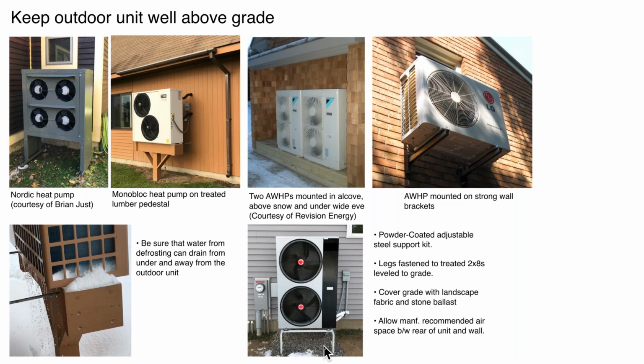And then just to show you what happens with one of these units when it goes into a defrost, if you look over here on the left, lower left, if you look carefully, you can see the water pouring out of the bottom of that unit. If that unit is just sitting on a concrete slab, what can and has happened is that water will tend to accumulate in the bottom of that unit. It won't fully drain away, or it'll run out of the unit and form an ice dam. Literally, it'll build almost a dam around the back side of that unit, and that's going to further hold condensate against that coil. And I have known of coils that have failed because of the expansion and contraction of ice when that condensate water is not properly drained away. So make sure that that unit can drain that condensate.